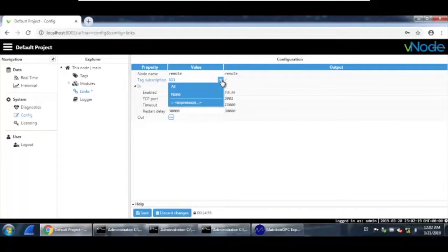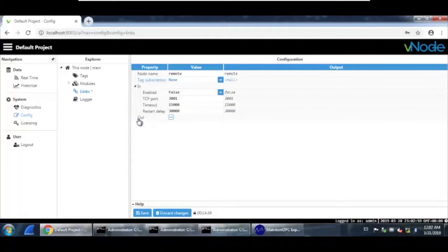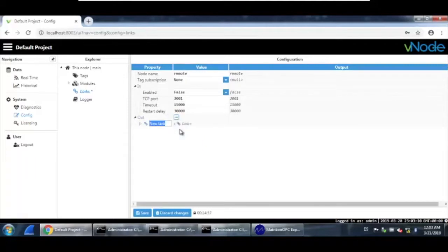Under tag subscription — this means that this Vnode, if you select 'all', will subscribe to any group of tags from another Vnode. But in this case, this Vnode will act as a sender, so we set tag subscription to 'none'. Also, under 'connection in', if this Vnode were acting as a receiver of data you would enable that option to true. But what we need to do is select 'connection out', which means you can send information to another Vnode. Here at the bottom, create a new link.